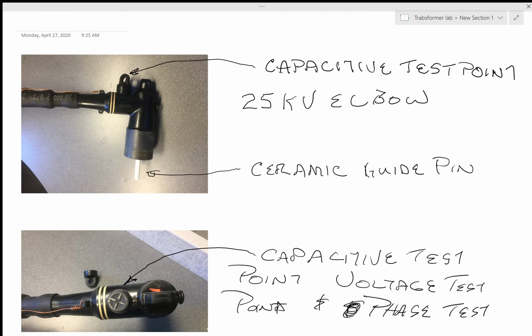We'll find out. Anyway, we have two types of systems on this campus. We have a 20 kV, 25 kV system, which is really 23.9 kV, and that is a VAB value, a line voltage value. It's mostly delta, because we don't run a neutral like we could run for Y, but you can have a grounded Y system, which is a 3-wire or 4-wire system also.